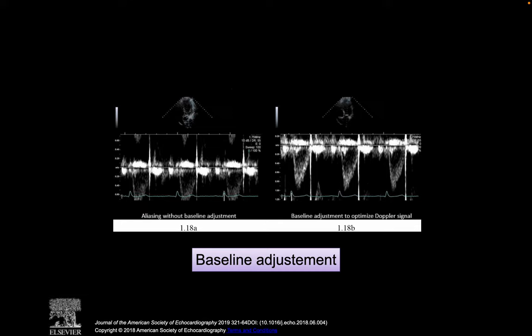When you have aliasing, when some parts of the signal are cut off and displayed on the wrong side of the baseline, sometimes it's enough just to shift your baseline and you might be able to get rid of that aliasing just by that simple measure. So shifting your baseline might be the only thing that you have to do.